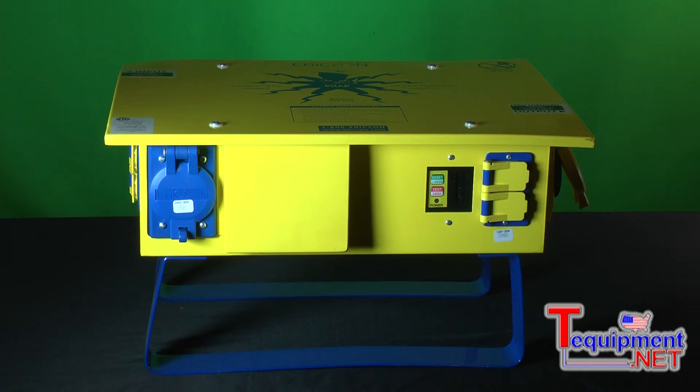We also make a NEMA 3 version that, as this model shows, has duplex flip-lid receptacles. It's designed and compliant with NEC standards for temporary power outdoors and is NEMA 3R rated. We also make a 4X rated version, so if you have a wash-down environment or someplace where you need to protect the unit from jetting water, we can provide NEMA 4 versions which are watertight. We also make a three-phase version for more industrial applications that require higher power.